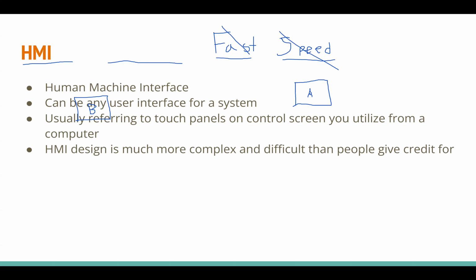If you go into a substation and see a display that shows you what all the power lines are doing, and you can click on something to have a relay open, open a breaker, something like that, then that would be an HMI, and that's something you can interact with. It's part of the SCADA system, and that's what they would be referring to with HMI.